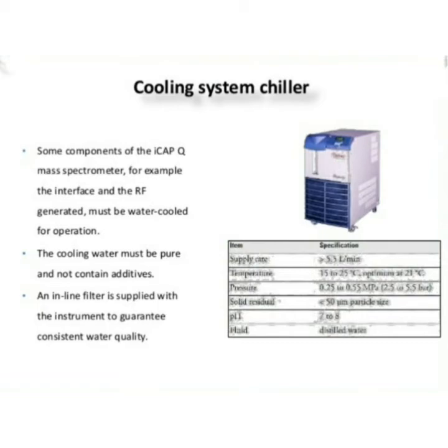Some components of the iCAP Q mass spectrometer, for example the interface and the RF generator, must be water cooled for operation. The cooling water must be pure and not contain additives. An inline filter is supplied with the instrument to guarantee consistent water quality. So for that reason we are using a chiller also.